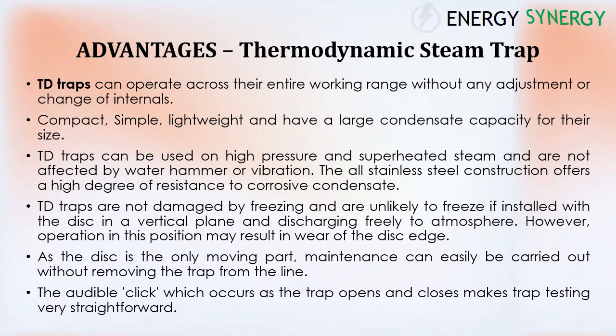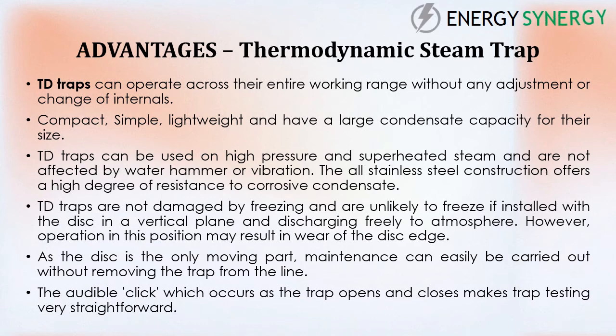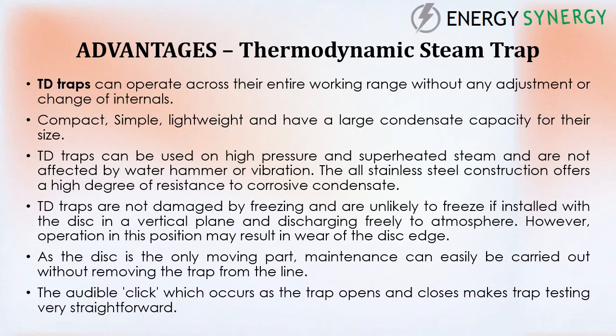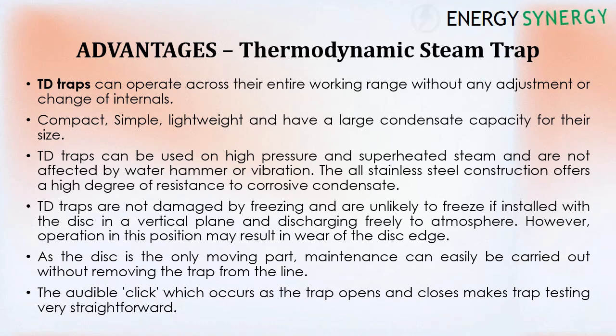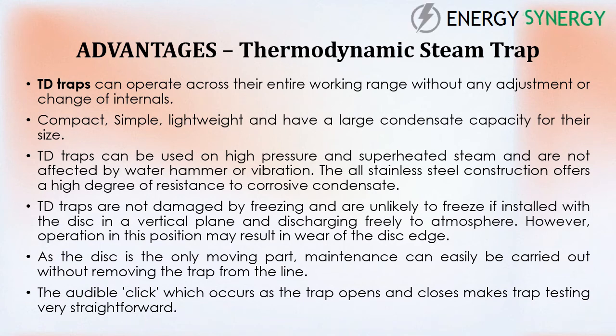The all-stainless-steel construction offers a high degree of resistance to corrosive condensate. (4) TD traps are not damaged by freezing and are unlikely to freeze if installed with the disc in a vertical plane and discharging freely to atmosphere. However, operation in this position may result in wear of the disc edge.